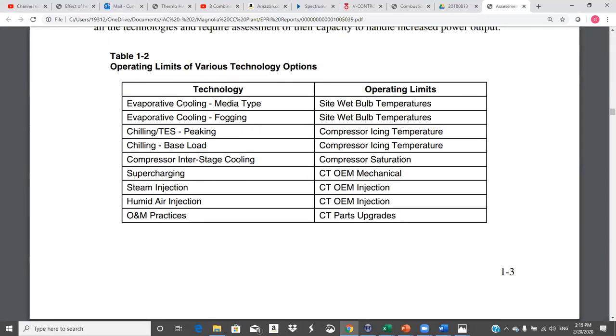These are the technologies that were investigated in this report, and like I said, I just printed a part of it for you. Evaporative cooling, a media type, is where you actually have this solid media that the air flows through. Fogging is like nozzles that just spray it. It's got a spray tree and the nozzles just blow it out. Operating limits are based on wet bulb temperature. Chilling, thermal energy storage: you can actually use chillers and make 40, 42 degree water and use it to cool this stuff down, and you get more performance. You have to be careful about ice, because as that air flows through the compressor, it tends to get cold. As it comes through that first stage of nozzles, because you drop pressure on it, it'll get cold and can cause ice formation and freeze up.